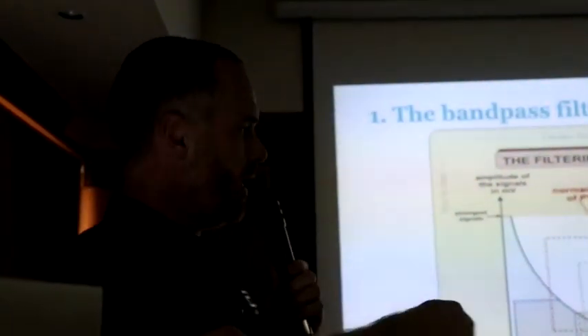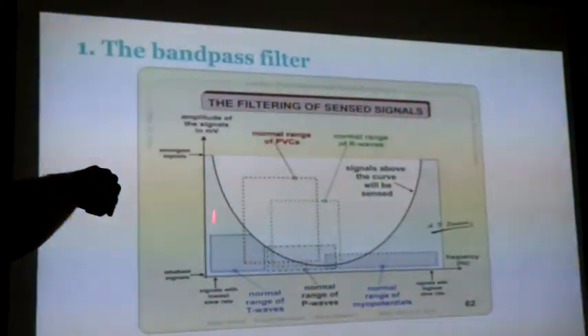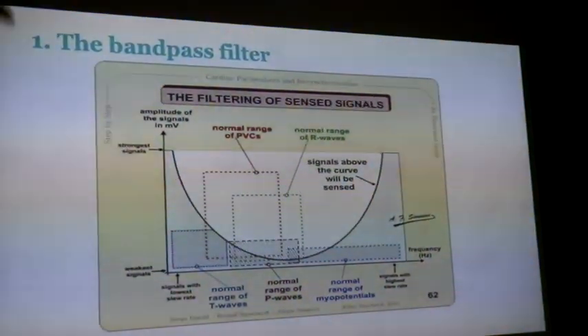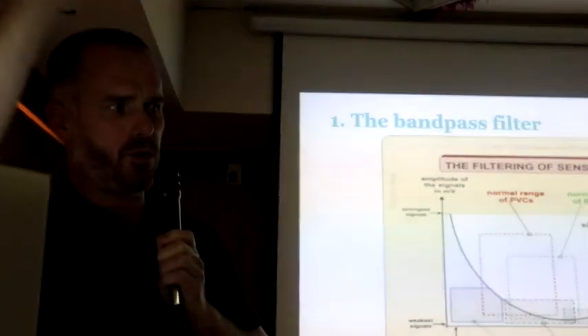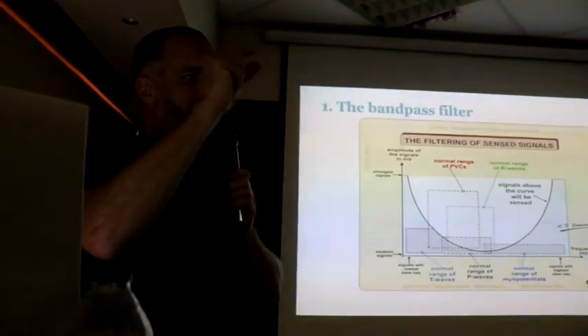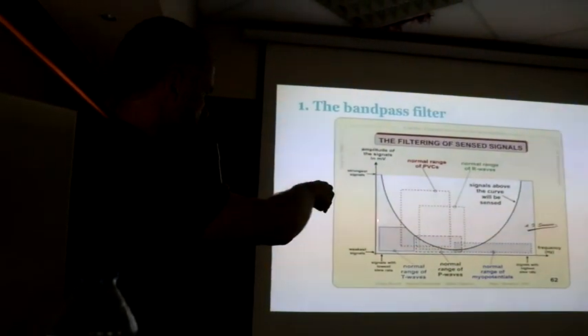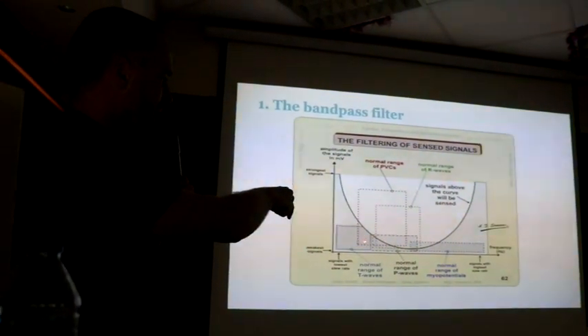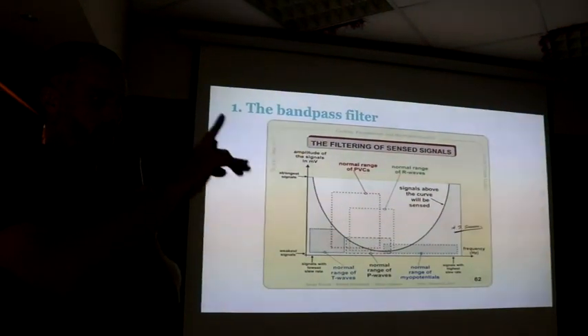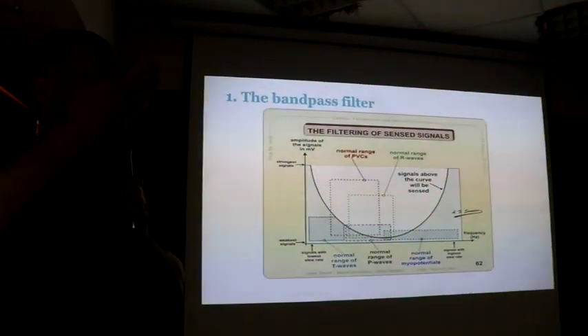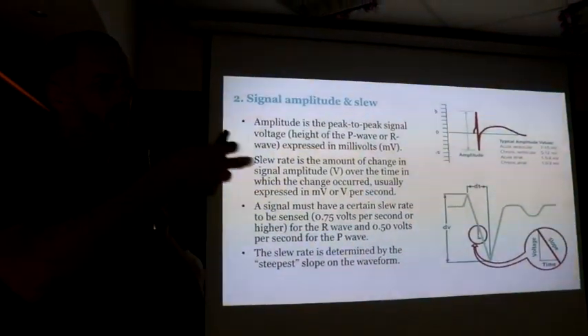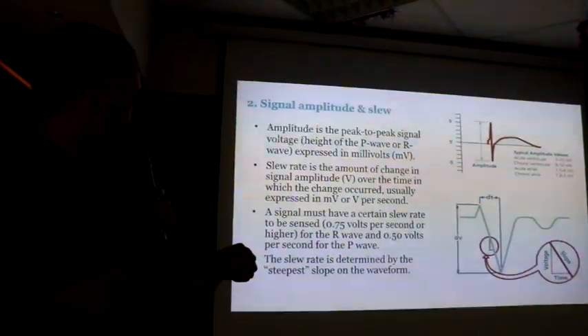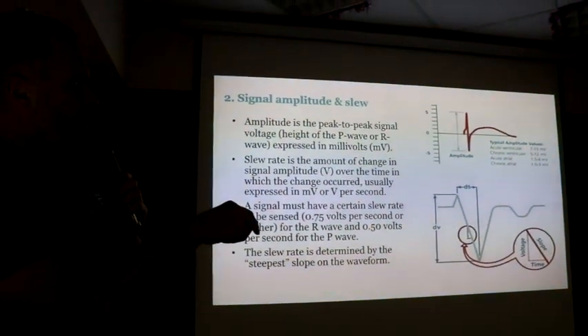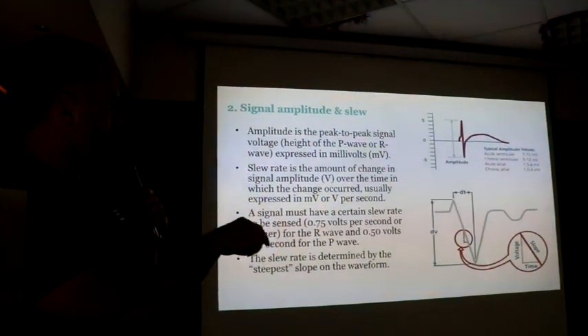So if I go back to the bandpass filter, if you have a bad slew rate, that means it's over here, right? This is low frequency. So a low slew, not a sharp signal, a gradual signal, is over here. And if you have a bad slew and a small signal, so small, low slew, you're here. And then the bandpass filter will flatten the signal, so the signal will be smaller. So slew rate is important, and slew rate will get reported on your device. So typically we're looking at kind of signals like this here. These are your acute signals.